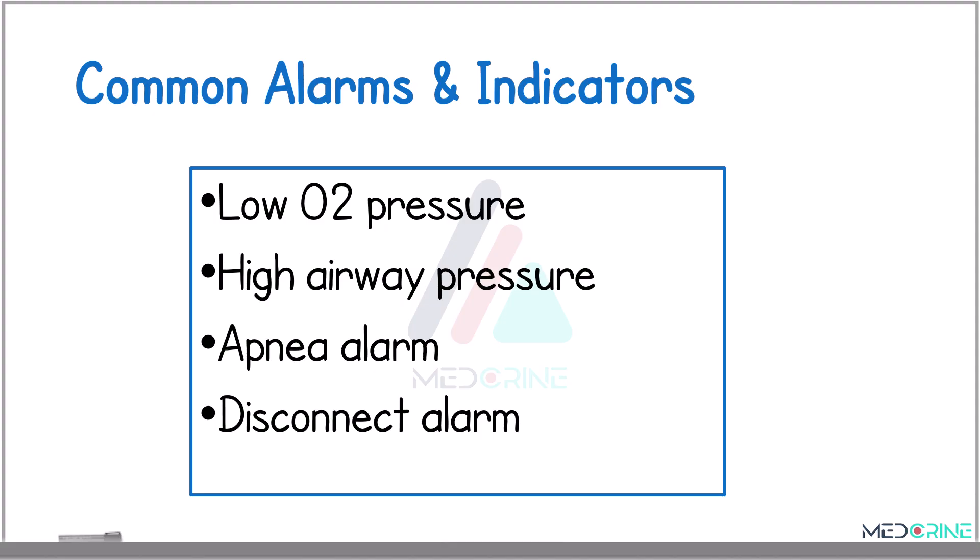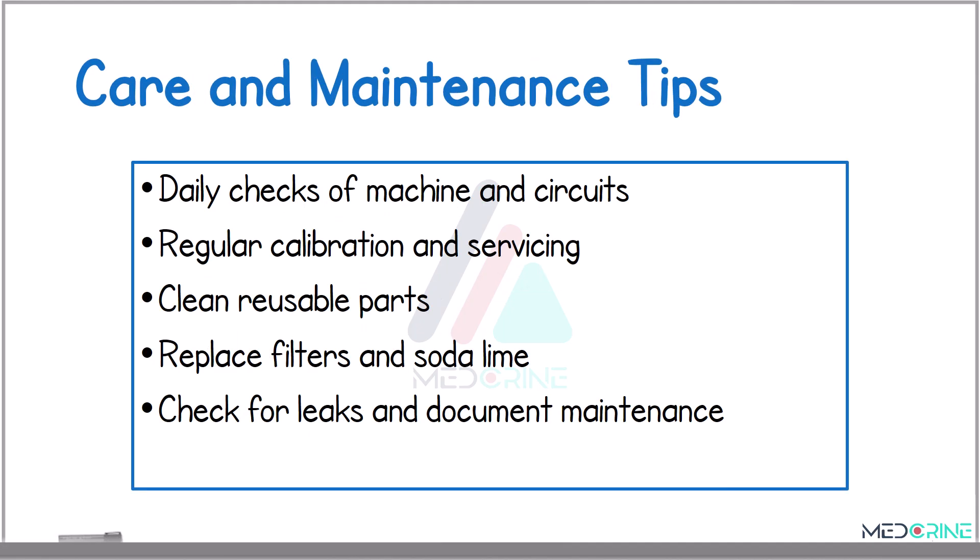The common alarms in anesthesia machines include a low-oxygen pressure alarm, a high airway pressure alarm, an apnea alarm, and a disconnect alarm. All of these are promptly addressed to ensure the patient's safety.